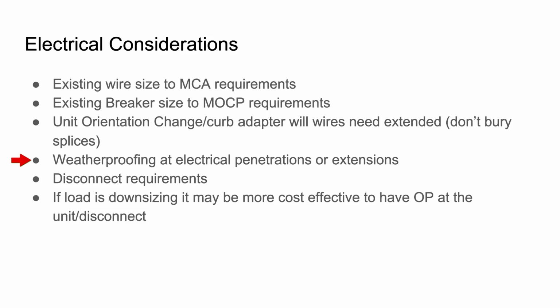I wanted to address weatherproofing at electrical penetrations or extensions, because this is something we did a poor job of early on. There would be knockouts in the bottom of the unit, and you'd think, well, we'll just pull our liquid tight out through there and run it over to the unit, we're good to go. But then how do you seal around the bottom of the unit if it's not in a weatherproof enclosure and there's a hole with something going through? You do have to terminate your covering in a weatherproof way.